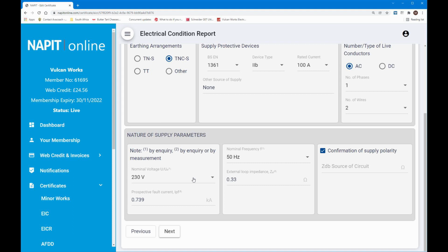As you saw in the video, the prospective fault current was 0.739. That was the higher of the two readings. It's a 50 Hz nominal frequency. Now this bit, as I've mentioned, I made a bit of a faux pas when I did the external loop impedance test when I was getting 0.4, and then I got 0.33. I got 0.4 because I didn't disconnect the bonding to the water pipes, which is a very long earth cable, goes from one side of the house to the other. That is why I was getting such a large external loop impedance, because I was getting a parallel path on a piece of earth bonding cable that was probably getting on for 15-16 meters long.